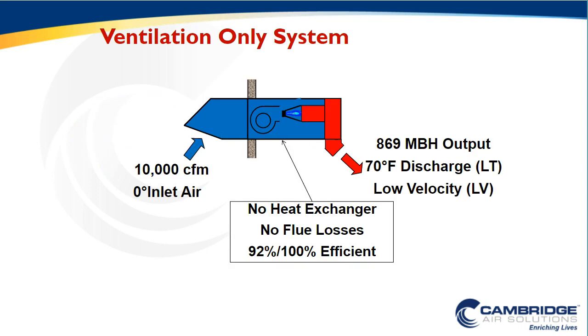Let's take a large warehouse that has a 10,000 CFM outdoor air requirement, and we have a 0 degree design temperature. In order to meet the air load requirements, I must heat that air from 0 degrees to 70 degrees, which is the internal design temperature for this building, and that equates to about an 869 MBH output. And if we are talking about energy efficiency, the most energy efficient way to heat this air is utilizing a direct fired makeup air system. With no heat exchanger, no flue losses, and a 92% thermal efficient system, I now have a very simple and very energy efficient way to heat the air load in the space.